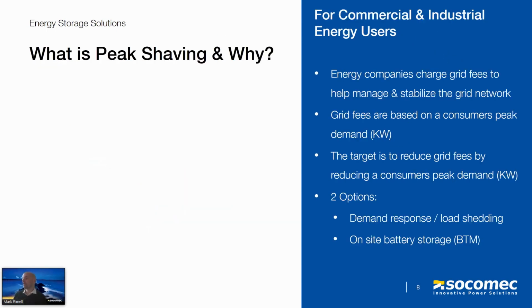So when we have a look at what peak shaving actually means and why it's important, energy companies charge grid fees to help to manage and to help to stabilize the grid network. Our grid fees are based on a consumer's peak demand, so their maximum kilowatts that they consume from the grid. And our target is, if we can reduce this peak demand, we can reduce a customer's grid fees. Ultimately, there are two options possible for doing this. We could look at demand response and load shedding, or on-site battery storage.